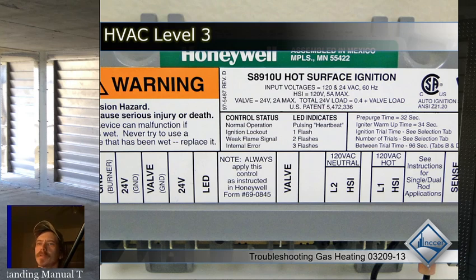Alright, defrost mode. You need to know the defrost sequence of operation. So you should be very familiar with the sequence of operation in defrost mode. I can probably check real quick in Google Classroom, in the class I set up for you guys. I have sequence of operations in there. There should be a handout that I posted there on sequences of operation. Yep, and that's got a typical defrost mode sequence of operation in it. I will pull it up real quick and just read through defrost real fast. That way we've covered it again.